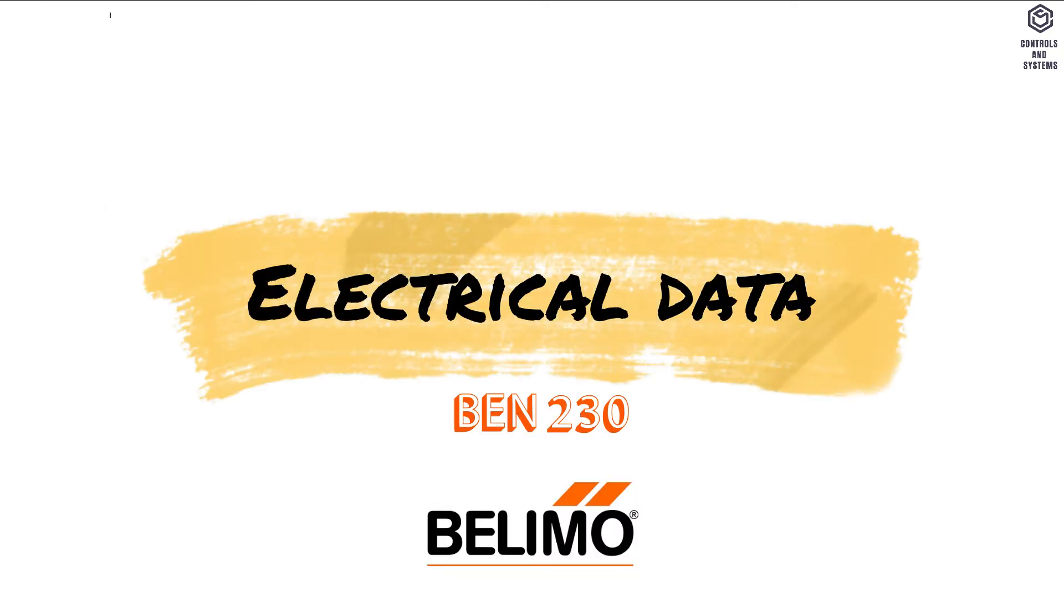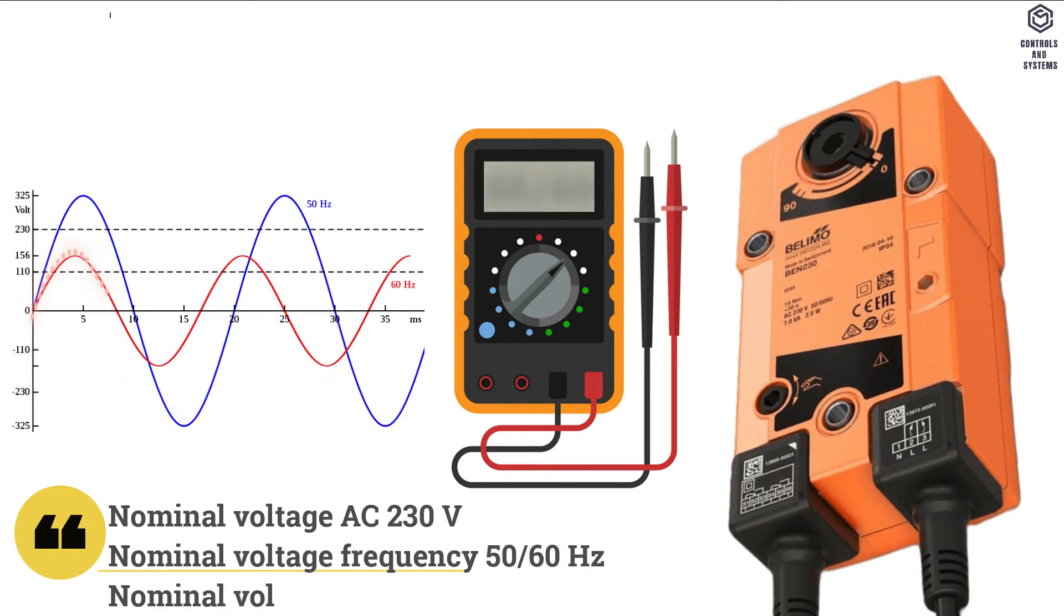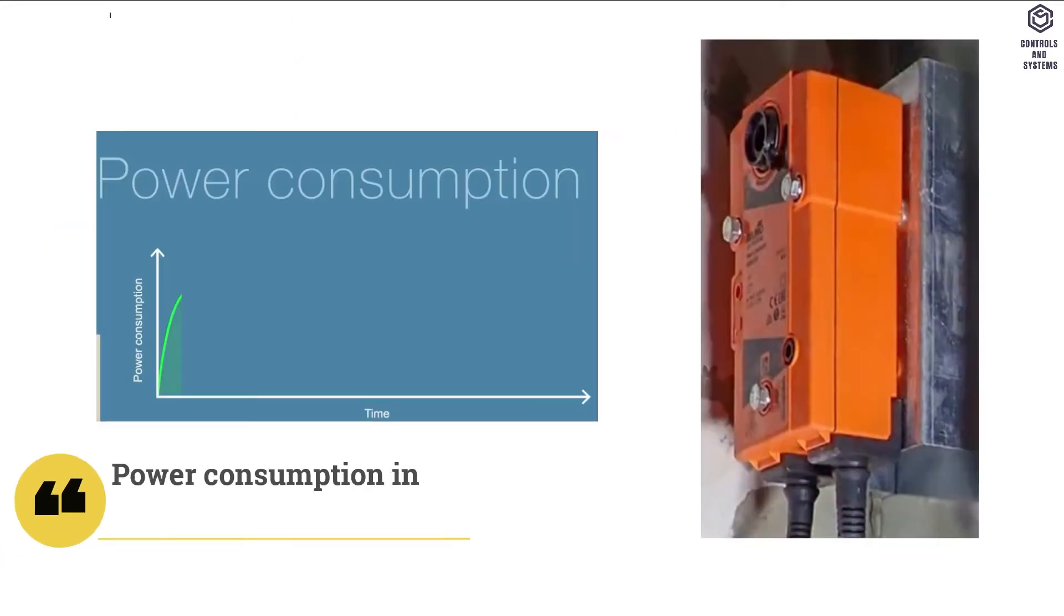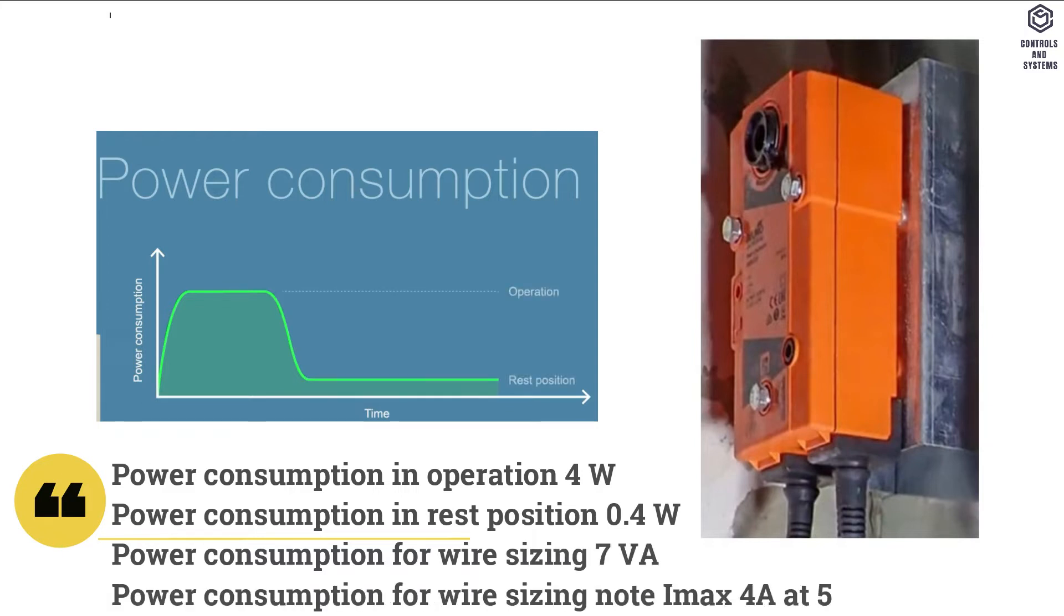Electrical data: nominal voltage is AC 230 volt. Frequency is 50 or 60 hertz. Power consumption in operation is 4 watt, in rest position is 0.4 watt, for wire sizing is 7 VA. For wire sizing note current maximum is 4 amps at 5 milliseconds.